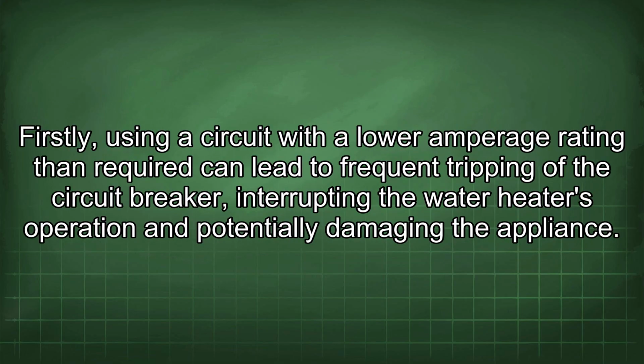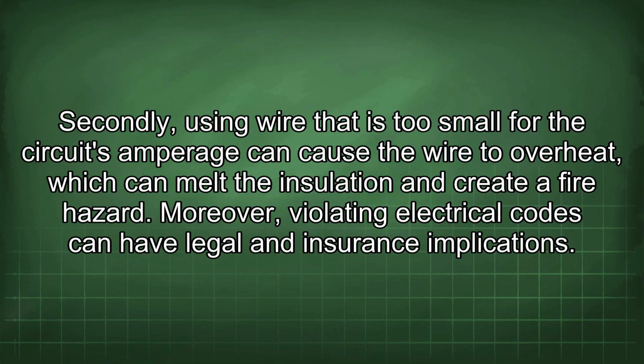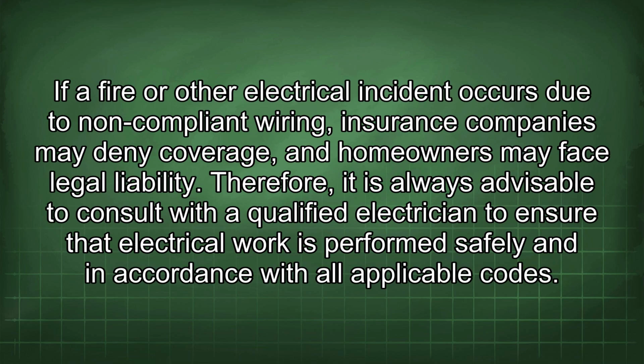Firstly, using a circuit with a lower amperage rating than required can lead to frequent tripping of the circuit breaker, interrupting the water heater's operation and potentially damaging the appliance. Secondly, using wire that is too small for the circuit's amperage can cause the wire to overheat, which can melt the insulation and create a fire hazard. Moreover, violating electrical codes can have legal and insurance implications. If a fire or other electrical incident occurs due to non-compliant wiring, insurance companies may deny coverage, and homeowners may face legal liability. Therefore, it is always advisable to consult with a qualified electrician to ensure that electrical work is performed safely and in accordance with all applicable codes.